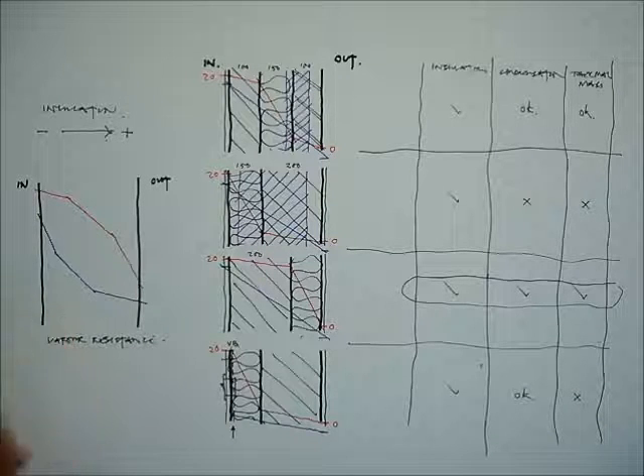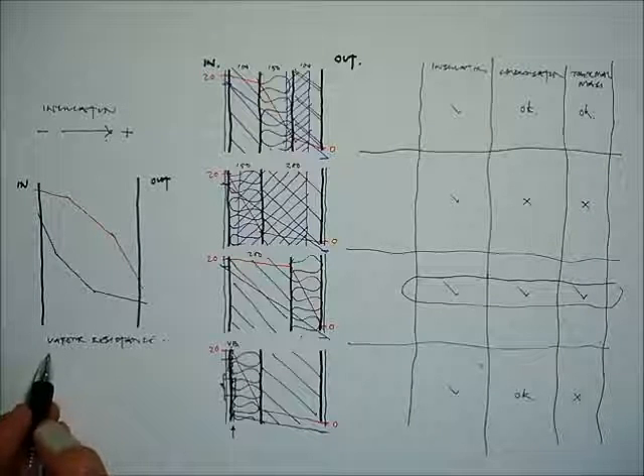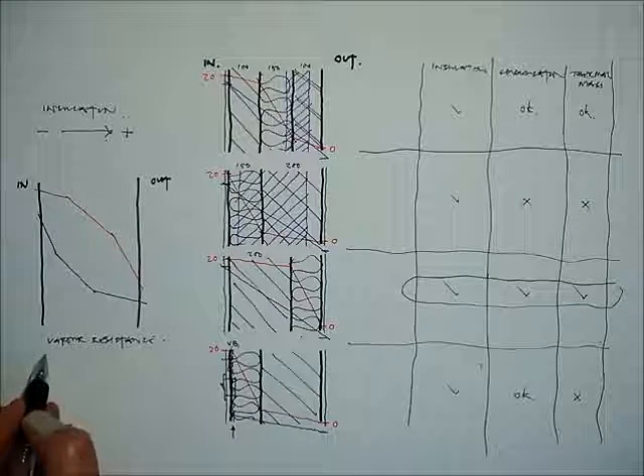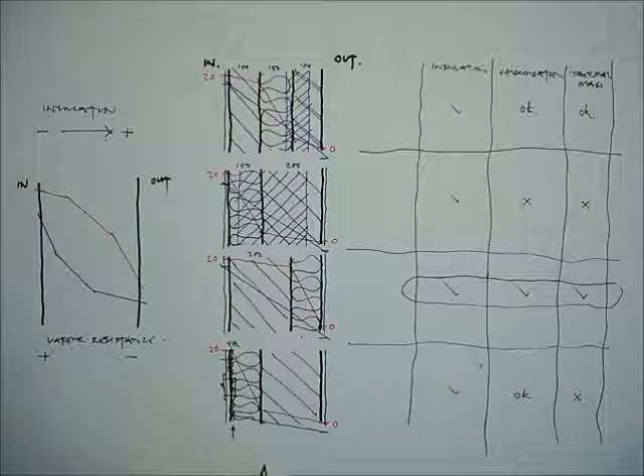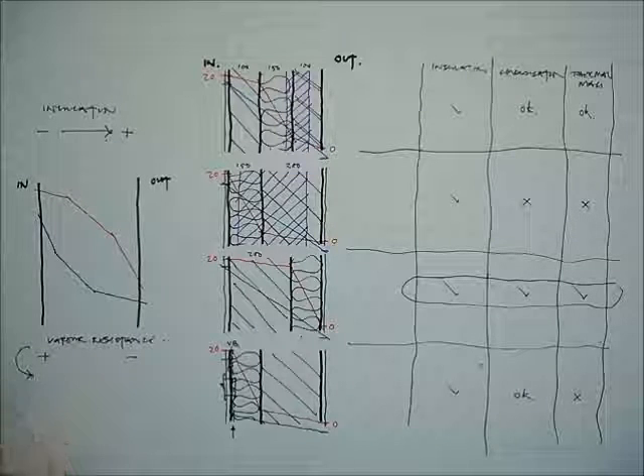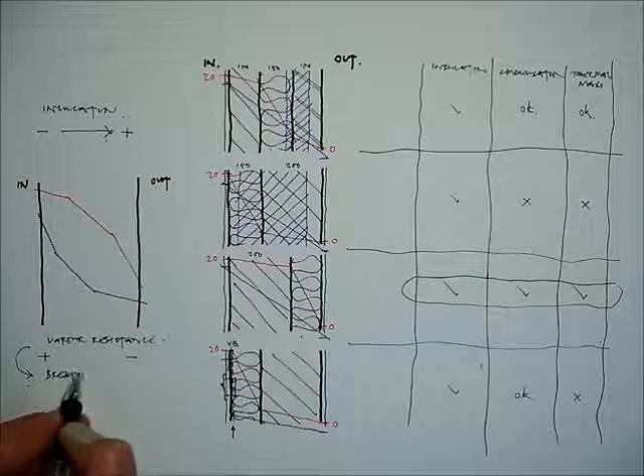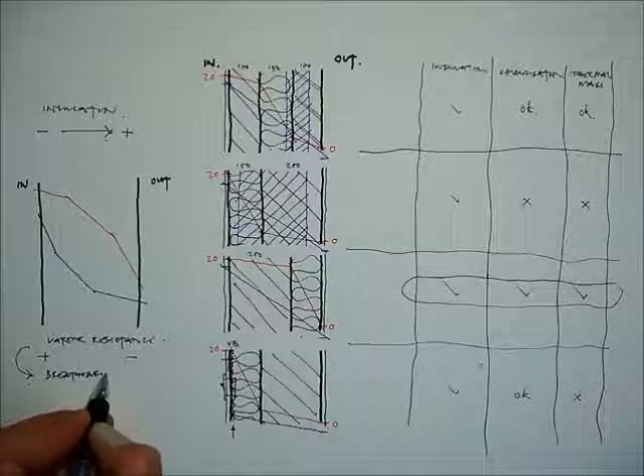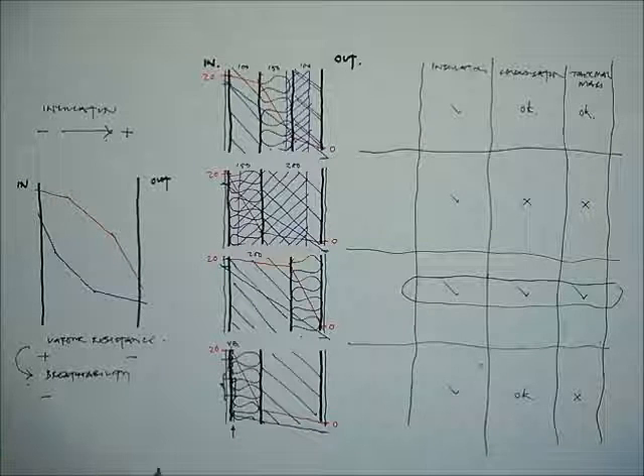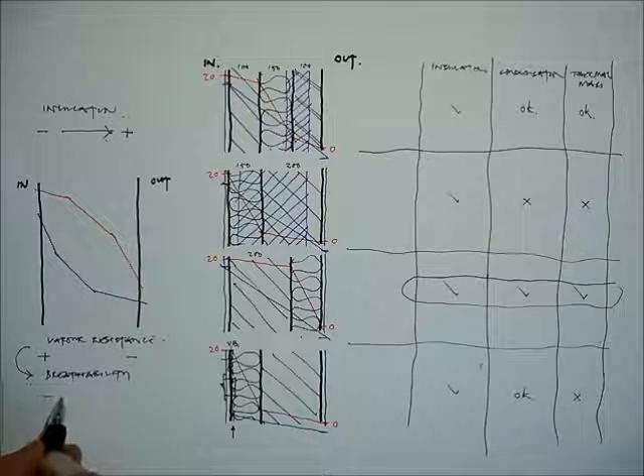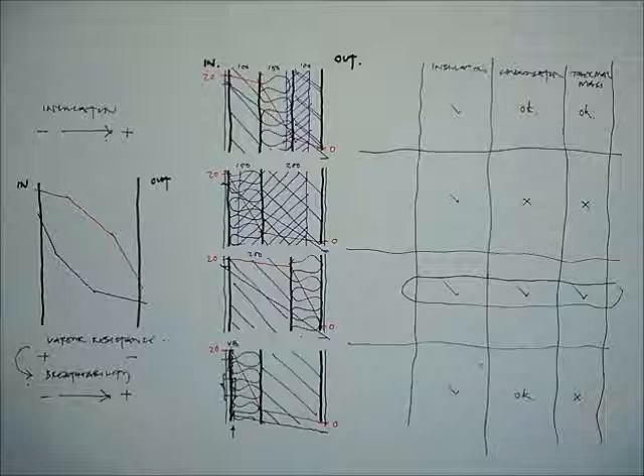Similarly, to get that form for the dew point temperature, the vapour resistance of the wall is high on the inside and low on the outside. But another way of thinking about that is breathability of the wall is low on the inside and that breathability increases as you move to the outside.